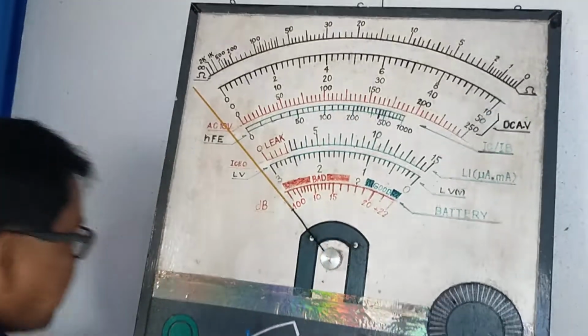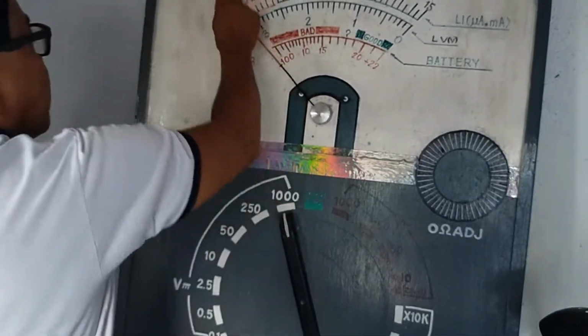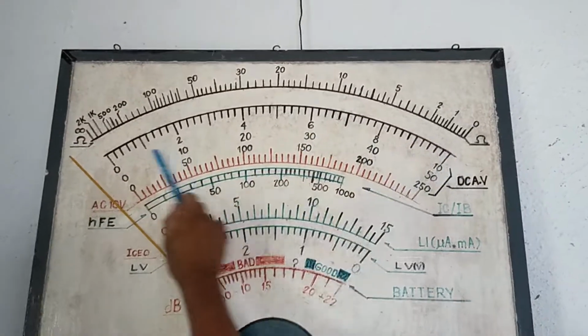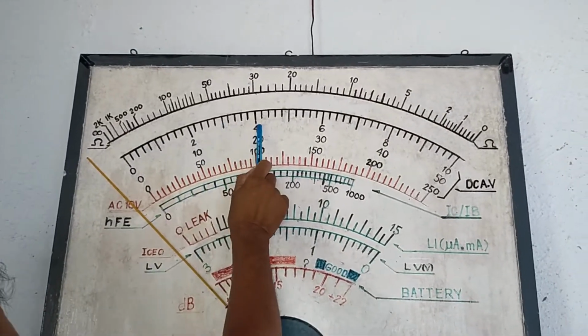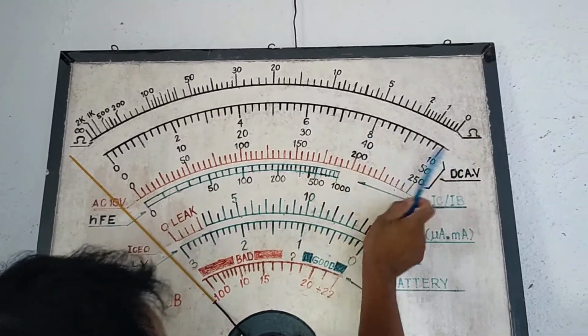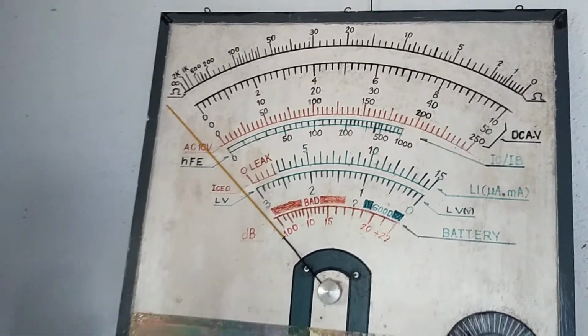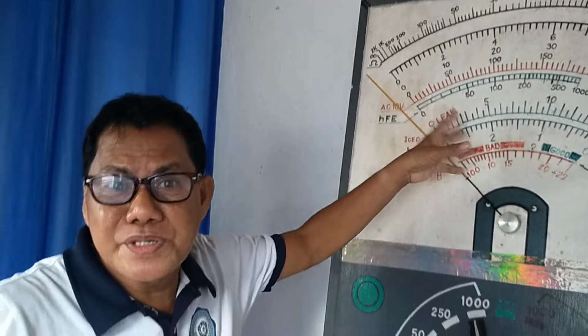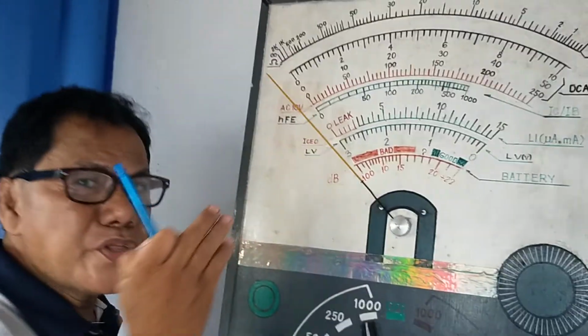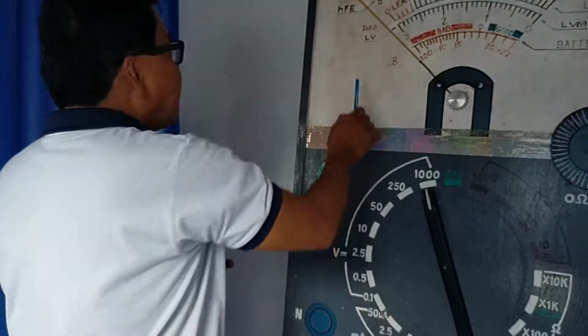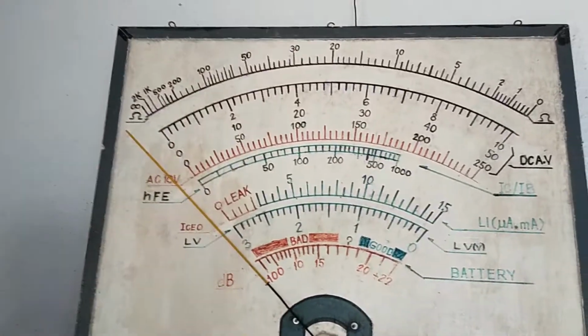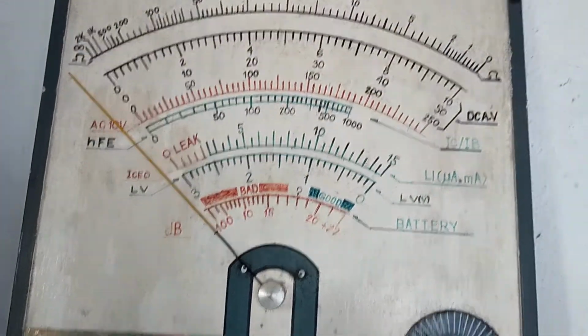Or what is the calibration of this voltmeter range 1000? So, if we are going to count the number of divisions, actually there are 5, 10, 15, 20, 25, 30, 35, 40, 45, 50. There are 50 divisions in this meter scale for voltmeter and ammeter DC. So, 1000 volt range divided by the number of divisions, which is 50, the quotient is 20. So, meaning to say, ang halaga ng bawat guhit dito ay 20 volts when using 1000.